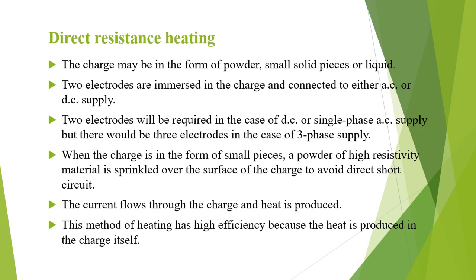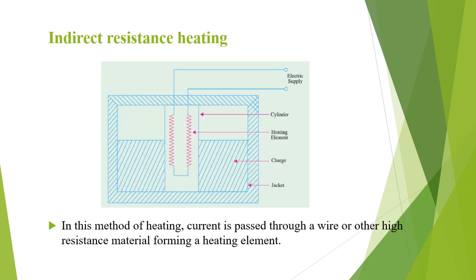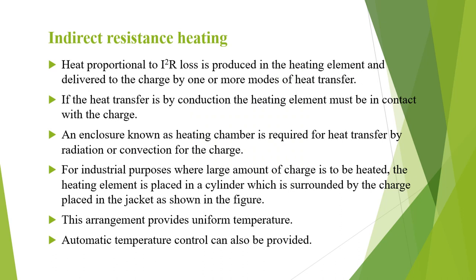Indirect resistance heating: in this method current is passed through a wire or other high resistance material which forms the heating element. The heat produced is due to I²R loss and is delivered to the charge by one or more modes of heat transfer. If heat transfer is by conduction, the heating element must be in contact with the charge. An enclosure known as a heating chamber is required for heat transfer by radiation or convection.